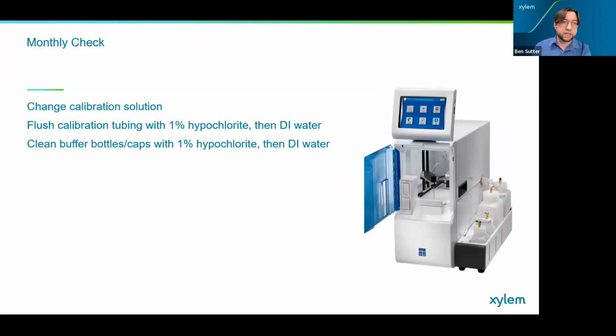Now it's time for our monthly check. You're going to change out your calibration solution. A lot of those are on 28 days, if not 14 days. So it's a good time every month to change those calibration solutions out. You want to flush your calibration tubing with 1% hypochlorite, that is bleach, and then DI water, or the cleanest water you have available, at least distilled. Please do not use tap water on this. And then you want to do the same thing with the buffer bottles and caps with the 1% hypochlorite. And then same thing, you want to use the cleanest water you have to flush that afterwards.